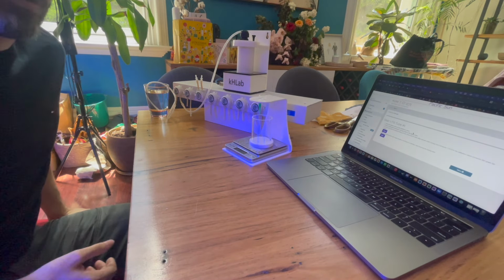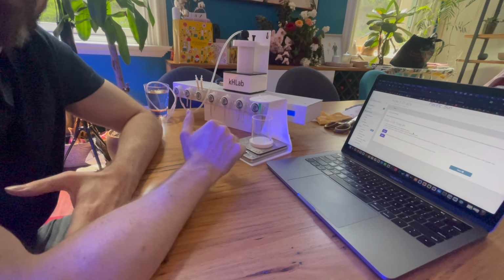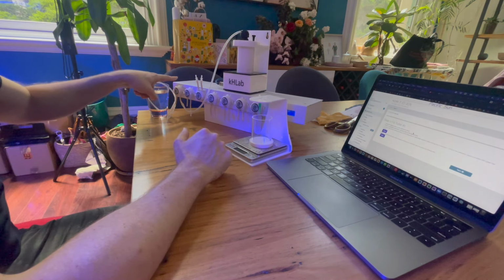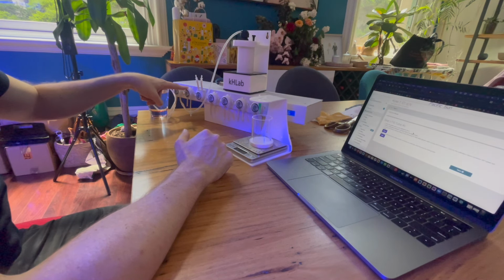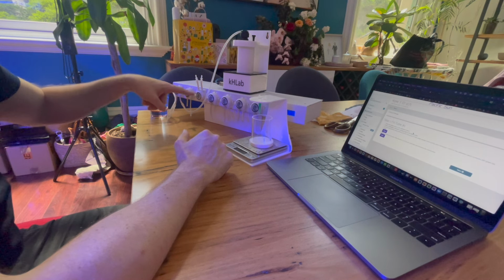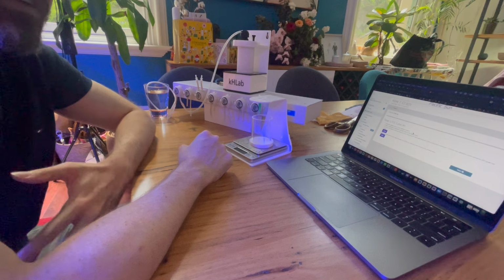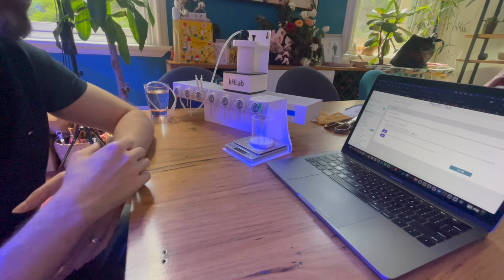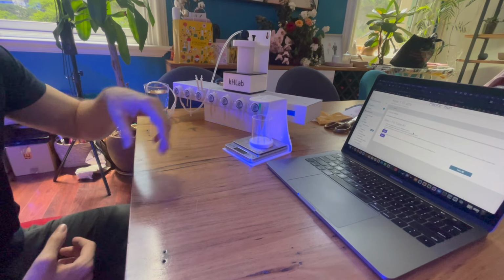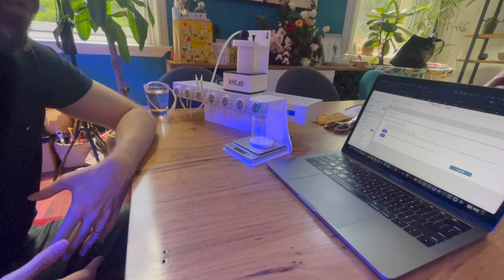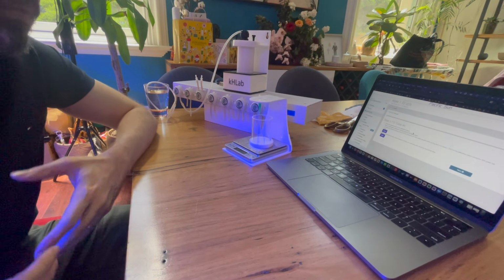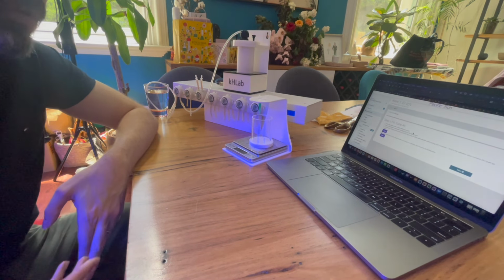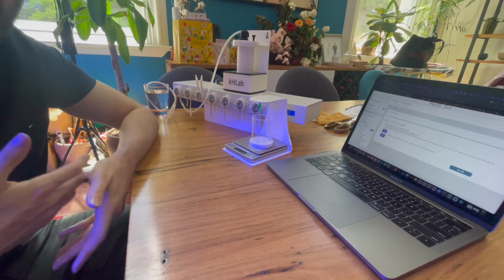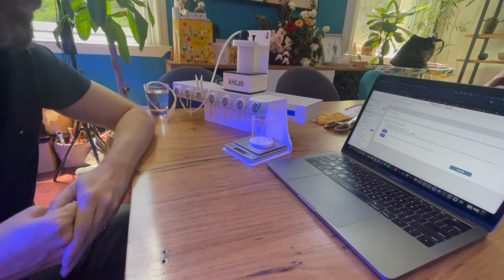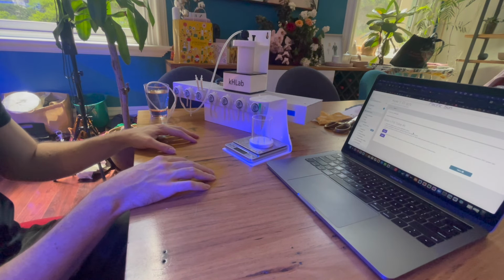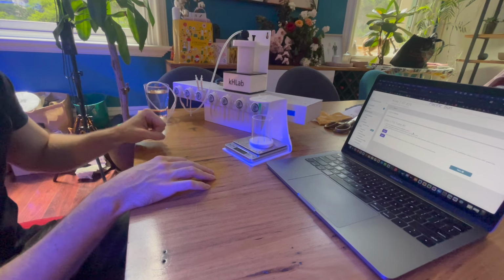Alright, so calibrating the pumps on the Core 7 is really, really easy. The main pumps that you need to calibrate are the first 3, being the salt water in, the reagent in, and wastewater out. It's important that these 3 pumps are calibrated accurately, because that will have an impact on the accuracy of the KHLab's alkalinity testing. The other 4 pumps are typically used for your dosing purposes, so whilst it's good to calibrate them and have them be accurate, a 1 mil drift here or there is not going to make much difference, given that they're most likely being used just for dosing fairly large volumes of alkalinity, magnesium, calcium, or trace elements. But where you want really accurate test results on your KH, it's very important to have particularly pumps 1 and 2 really accurately calibrated.